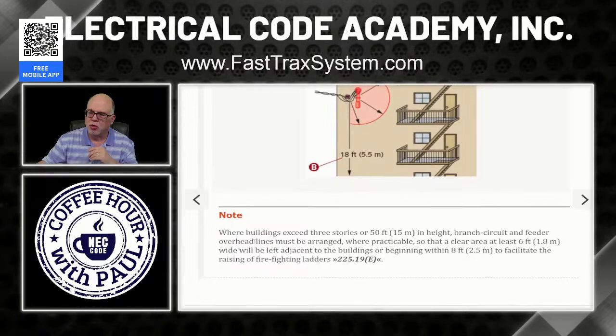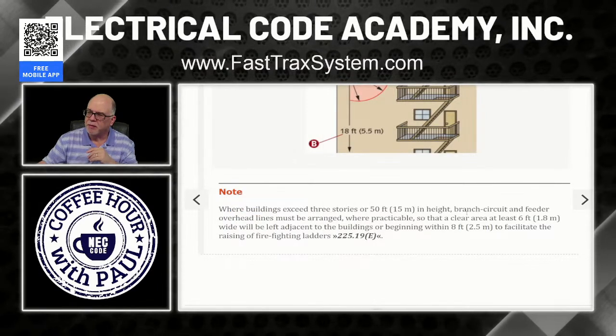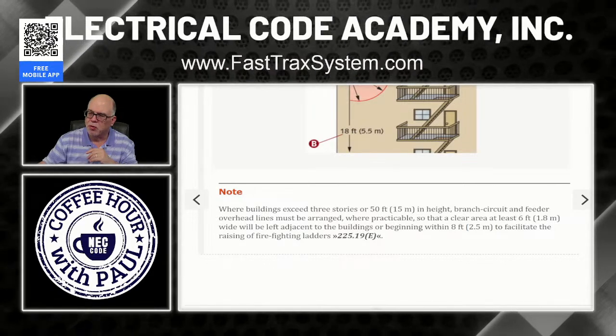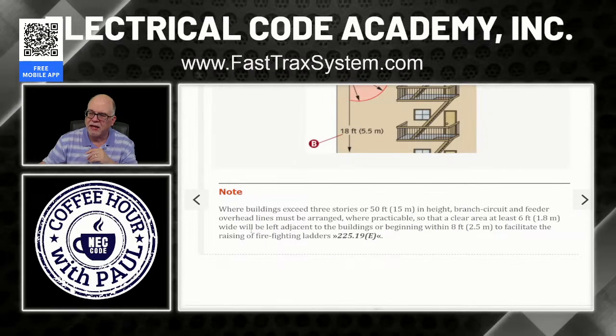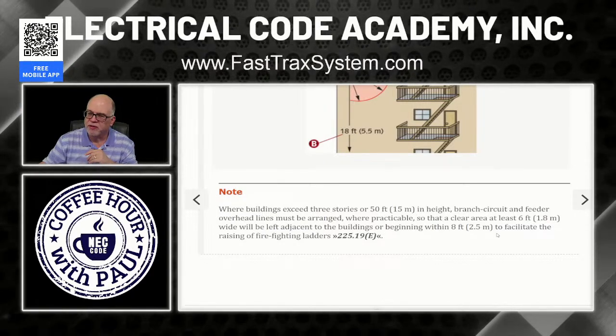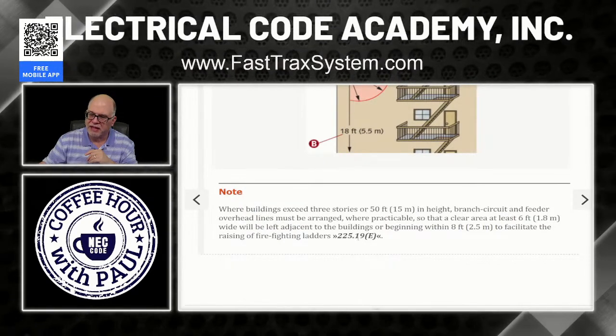But let's look at this note real quick. So the note says, where a building exceeds 3 stories or 50 feet in height, branch circuits and feeder overhead lines must be arranged where practicable so that a clear area of at least 6 feet wide will be left adjacent to the building or beginning within 8 feet to facilitate the raising of firefighter ladders. That's 225.19(E).